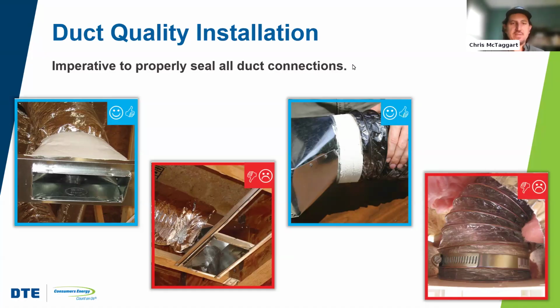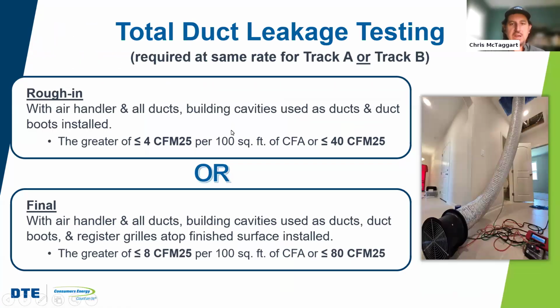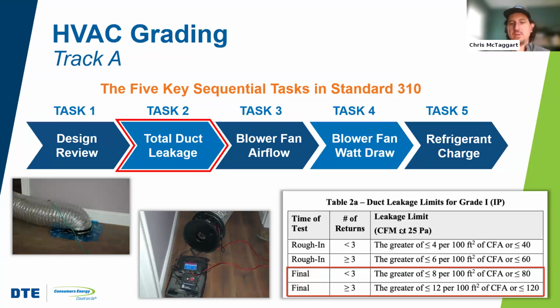Yeah, I want to go back and just clarify this just to make sure we're clear on this. When we talk about leakage, we're talking about leakage per floor area. So when I say like 12%, the reason why I say that is it's 12 CFM tested at 25 pascals per 100 square feet. So in other words, if you divided 12 divided by 100, that would give you 0.12 or 12%. So you could either say it the long way, so 12 CFM 25 per 100 square feet of floor area served, or you could just say 12% leakage.